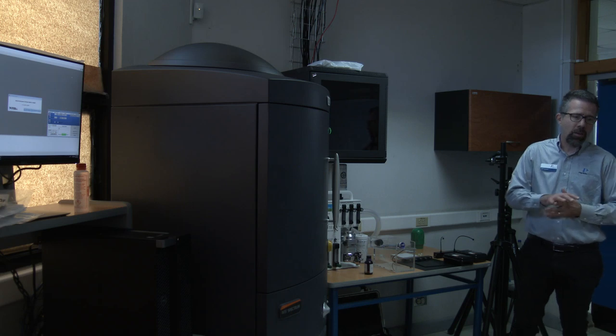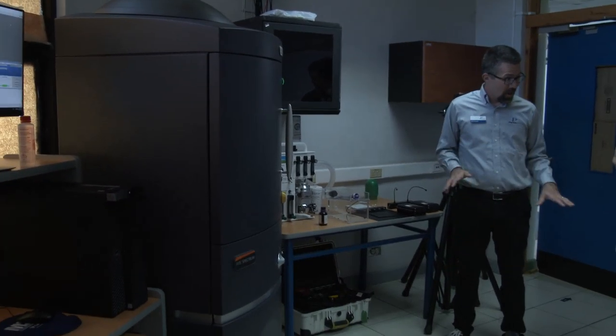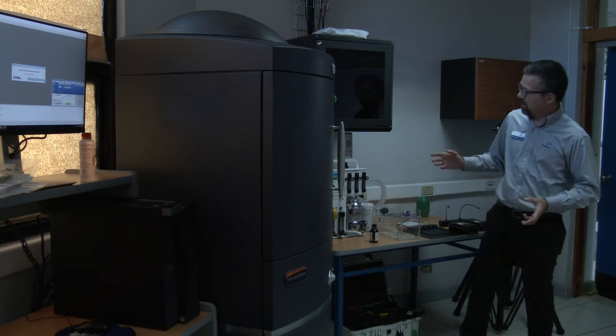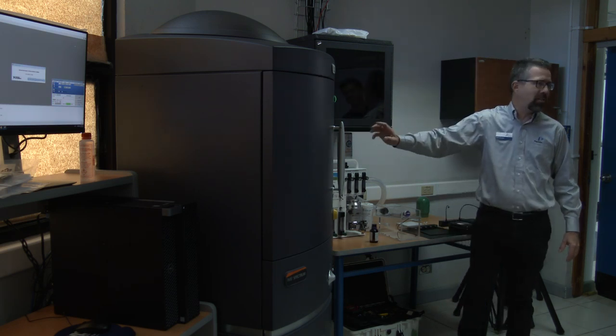First, when we come here, we want to make sure that we're able to use the system. In order to use the system, we need mice. And in order to get mice going, we need the anesthesia system to work. So I'm going to start with the anesthesia system. The anesthesia system uses oxygen as a carrier gas. There's a regulator up there, and the regulator is preset to 50 psi.